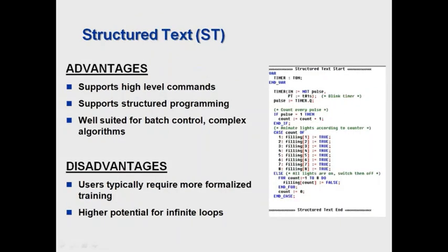Then there's structured text, which can be used, and it can be intermingled within derived function blocks or programming sections as discussed before. It supports high-level commands, supports structured programming, and is well suited for batch control and complex algorithms. For those that are very familiar with structured text, you can use the IF and IF-ELSE statements, looping statements, defined variables, FOR loops, etc., that are typical in structured text languages.